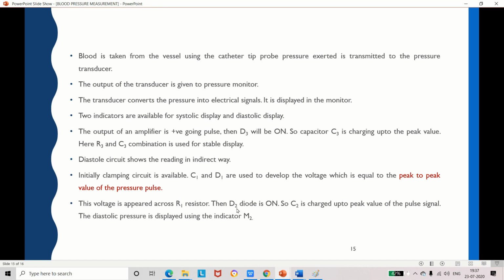As already told, this diode will turn on so that C2 is charged up to the peak pulse value, and we can measure the diastolic pressure in M2. The formula for measuring diastolic pressure is: M2, the diastolic pressure, equals the peak systolic value minus the peak to peak value of the pressure pulse. So by subtracting both, we can get the diastolic pressure.